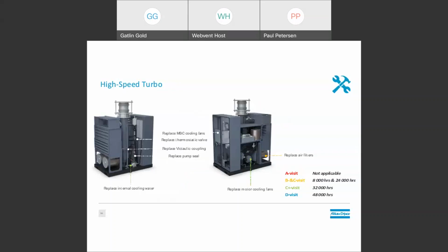The HighSpeed Turbo blower offers the lowest maintenance of any type of unit. They typically require annual filter changes and water or coolant changes anywhere between 2 and 5 years. Beyond that, down the road are some items that are typically not thought of when looking at high-speed turbo blowers, such as replacing cooling fans, water pumps, other appendices like valves and actuators, which can be anywhere from 10 to 15 years down the road.